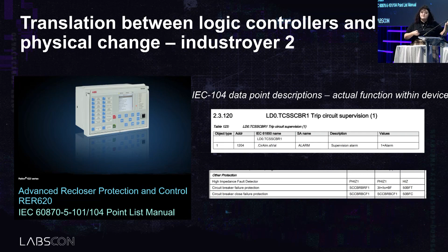If you go back to the vendor documentation, in this case ABB, you can start to map the IOAs back to the actual engineering functions they refer to. These numbers in the configuration file map to the data points describing the engineering function, and later in the documentation you can translate those to what it's actually changing. In this case, it was both supervision alarms and circuit breaker failure protection - those were the things being turned off and on from the Industroyer 2 configuration file.